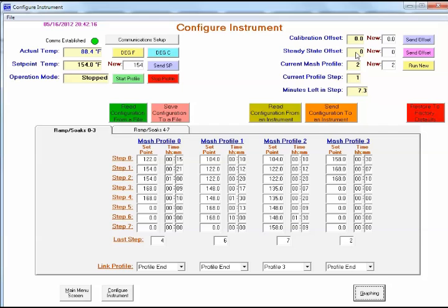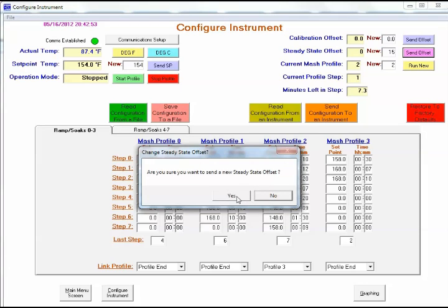During the soak period, everybody's system will just settle in maybe a couple tenths above or a couple tenths below the set point. And it's absolutely fine to just leave it that way. If for some reason you want to increase that just a little bit, you can add an additional amount of percent on time for the cycle as it runs its 30-second cycle. So you can just enter another number in there simply by adding, say, we want to go another 15% to kind of just raise that temperature just a little bit. We can go send offset and then click yes.